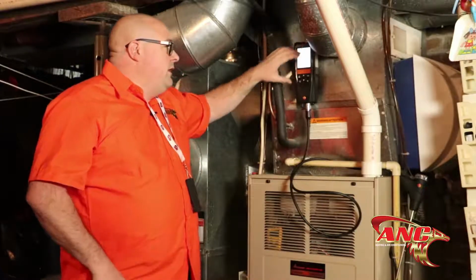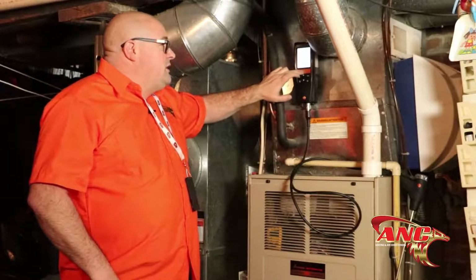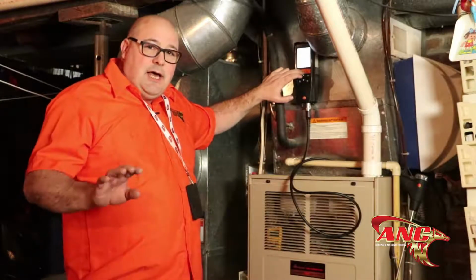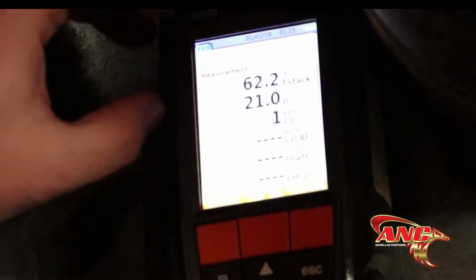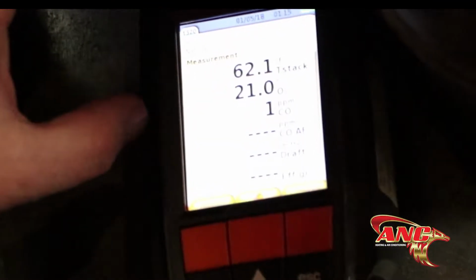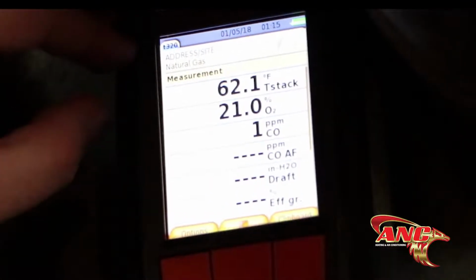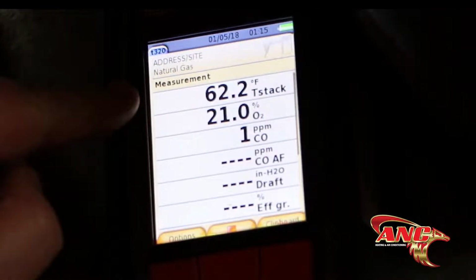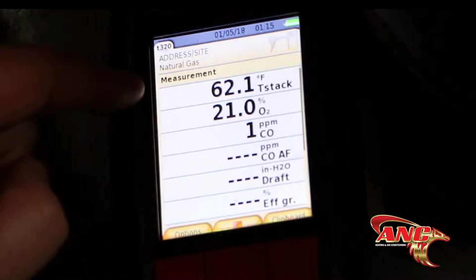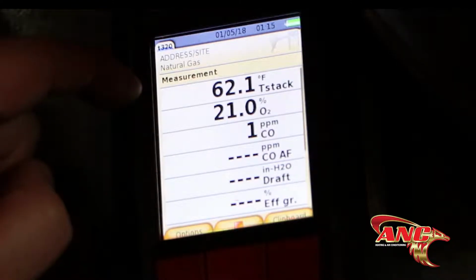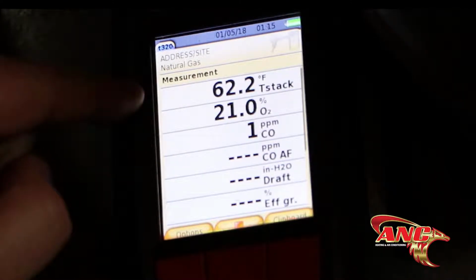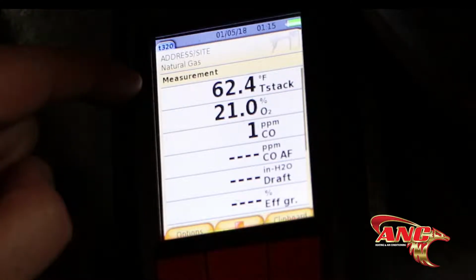But it tells us more than that. So you can't just have the analyzer, somebody's got to know how to use it. What we're really looking for is red flags on readings when we're doing maintenances. The top number here is going to be the stack temperature. On a 90% PVC vented furnace, I want to see a temperature somewhere between 95 and 110 degrees.